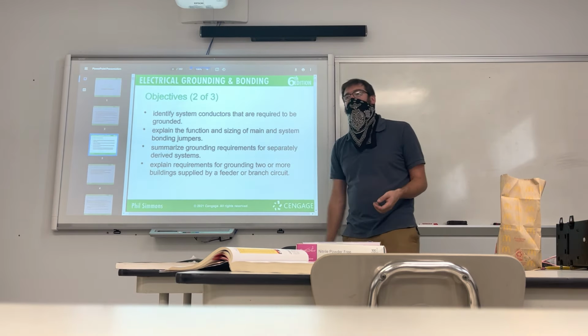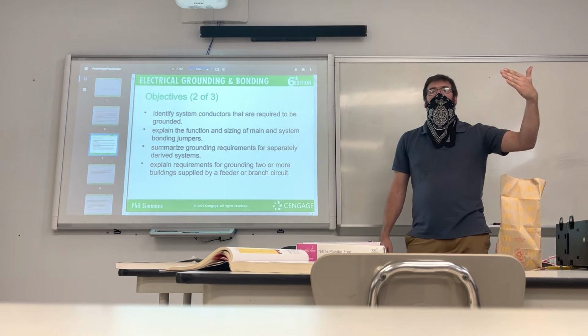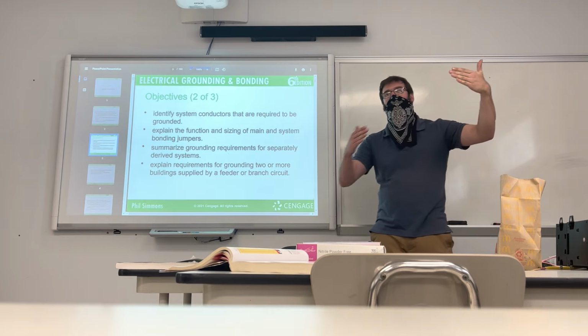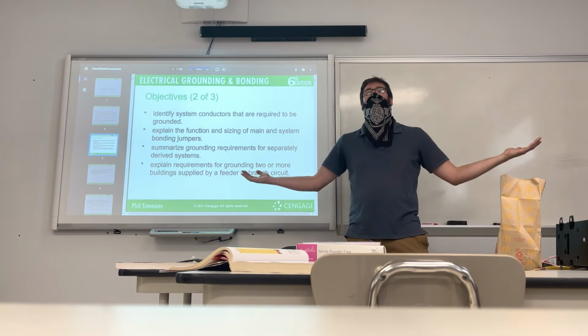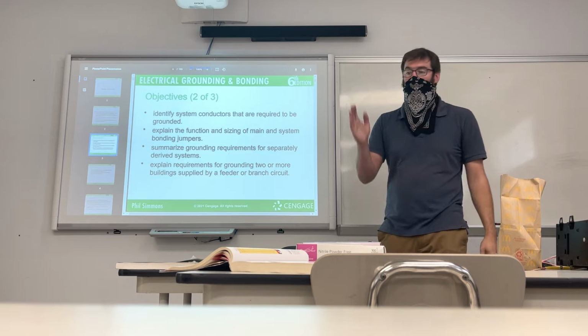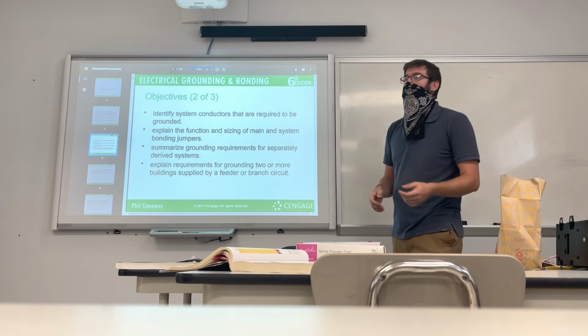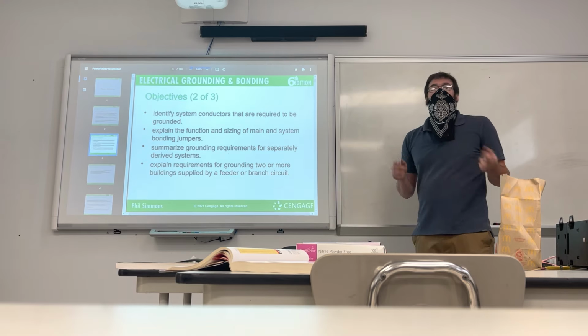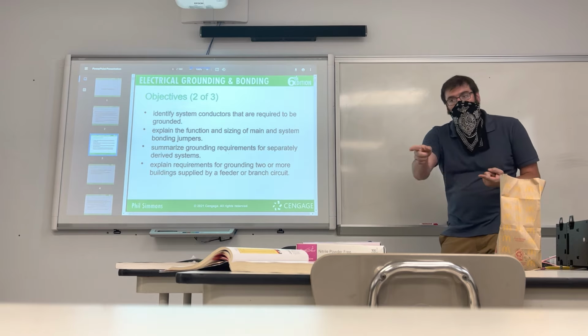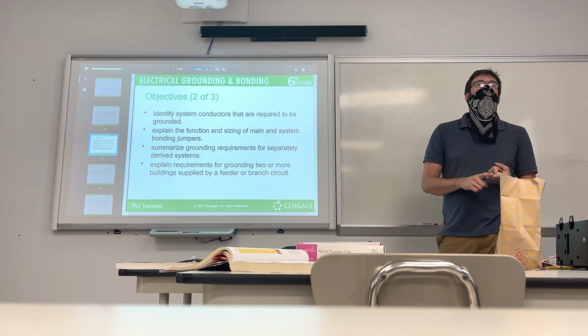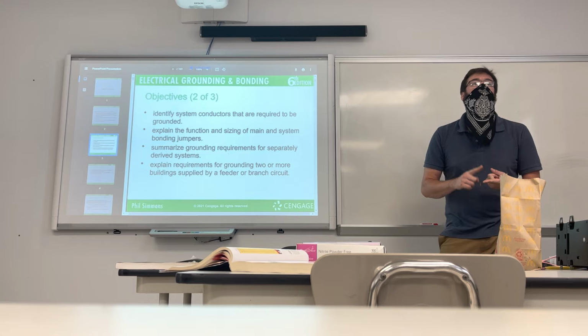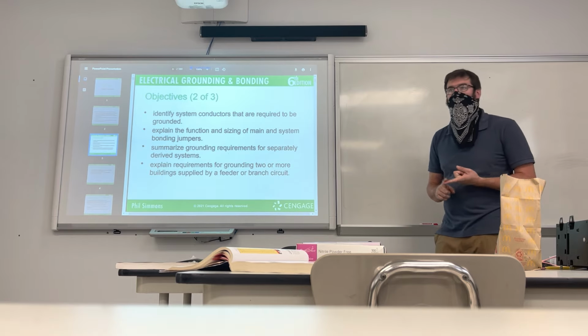If you look at your service coming in, it says I have 200 amps coming in. Okay, 200 amps has to be grounded with 4-gauge copper. How easy is that? No math or nothing involved. You just look at a scale. So you guys are electricians. You're smarter than hell. Are you going to know everything in that book? Absolutely not. But when the situation comes, are you going to know where to look? That's the important thing. Where to look.